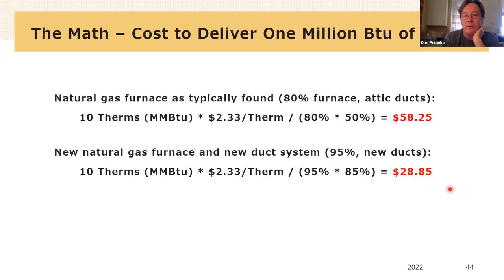For easy comparison, the way that this particular example is laid out is in cost to deliver 1 million BTUs of heat to a space, right? So the efficiency of the equipment is one factor, and I want to point these things out. The first example is an 80% furnace, right? That 80% in this math here is the equipment efficiency.